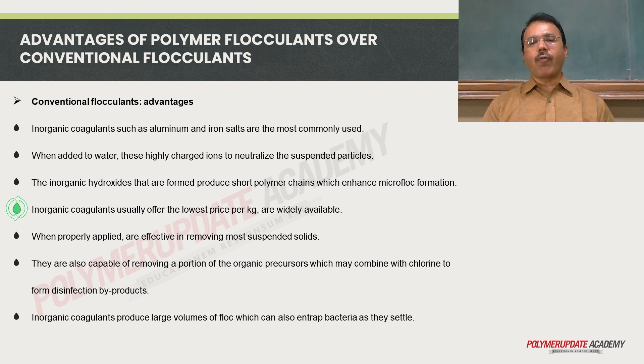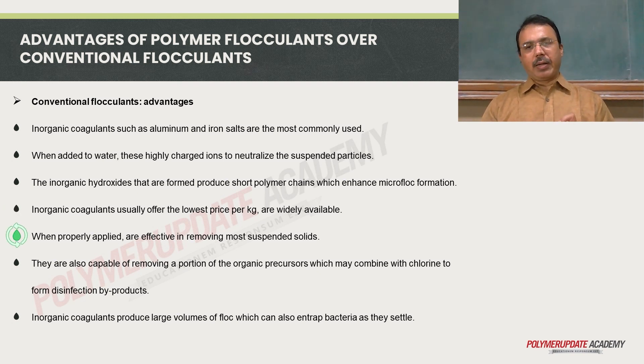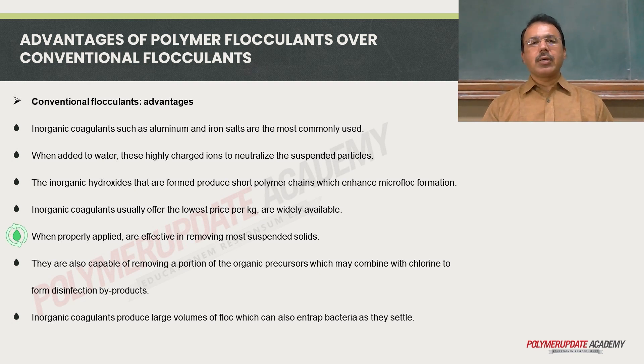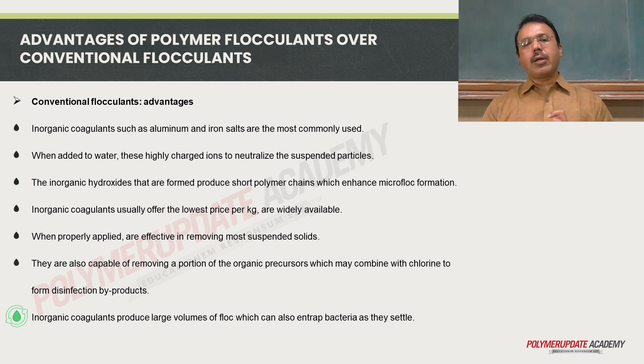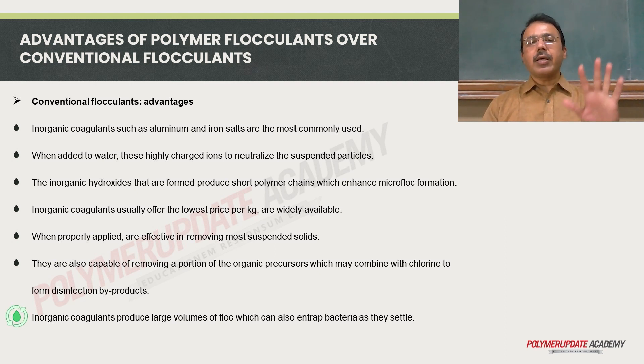Inorganic coagulants usually offer the lowest price per kilogram and are widely available. When properly applied and selected, their effectiveness in removal of suspended solids is very good. They are also capable of removing a portion of organic precursors, which may combine with chlorine to form disinfection byproducts. These inorganic coagulants produce large volumes of flocs, which can also entrap bacteria as they settle.